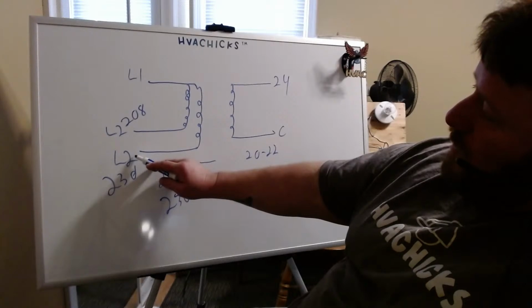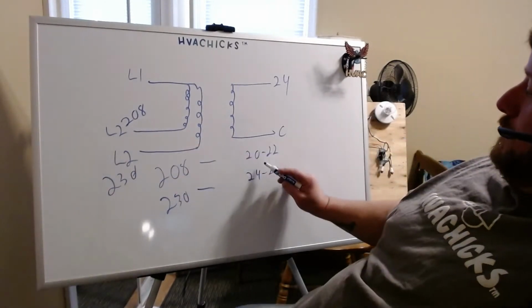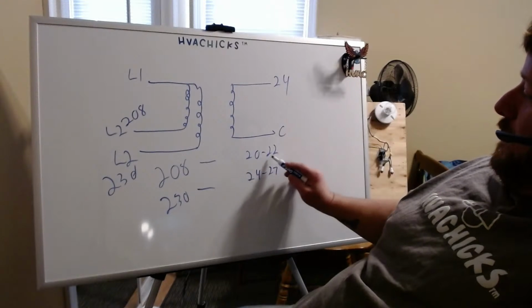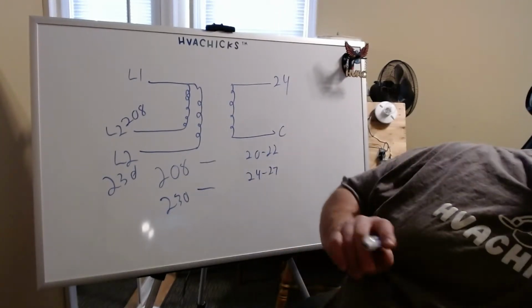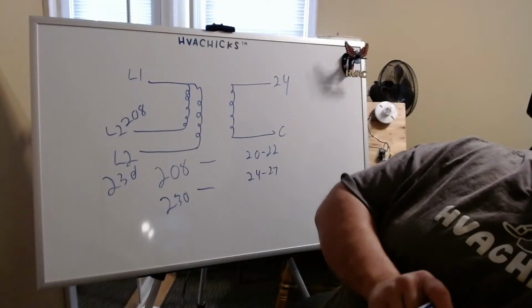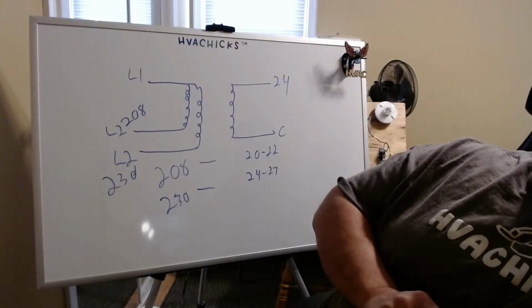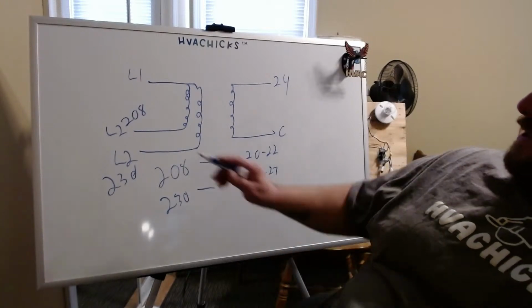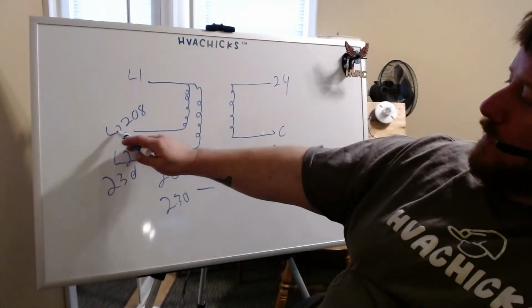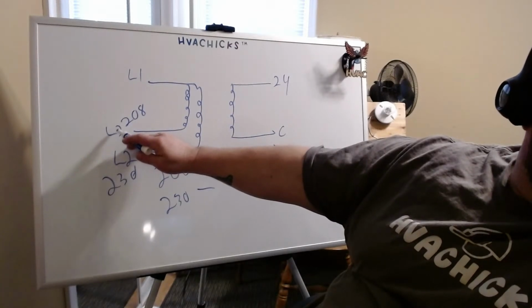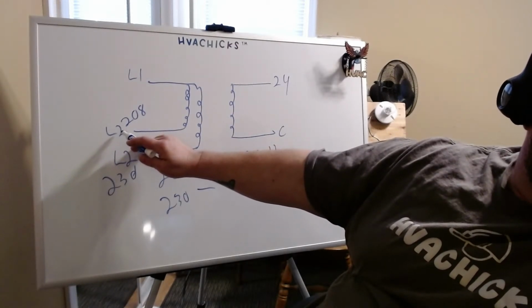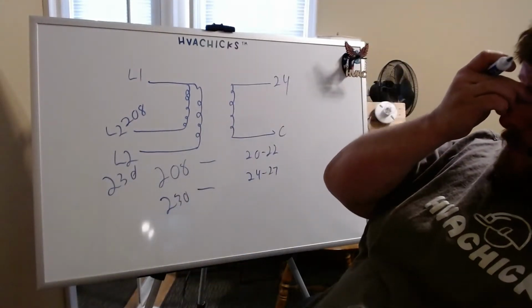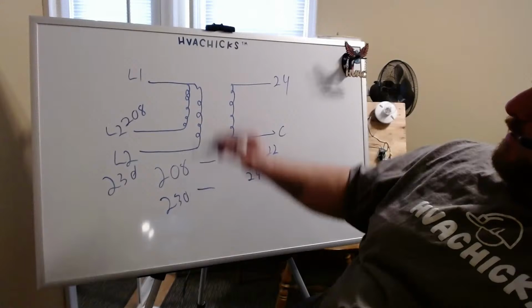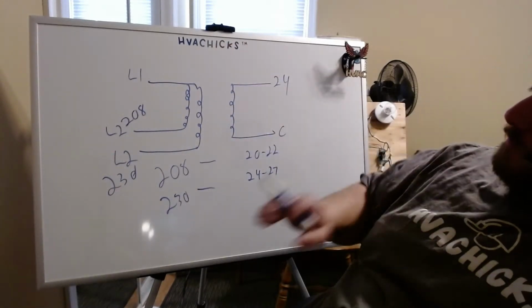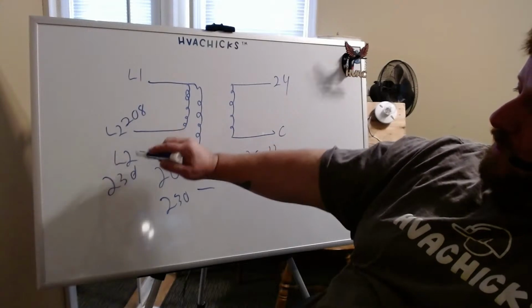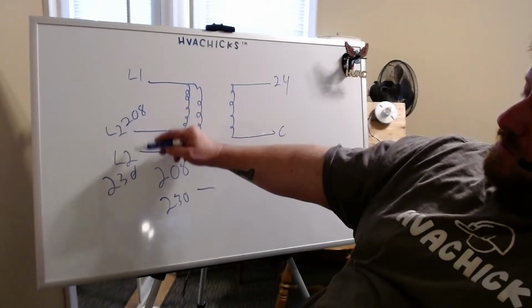If I don't move this 208 wire over to the 208 tap, I'm going to be getting this voltage right here. It can cause contactors and relays to overexert themselves to try to get the 24 volts to close those coils and make them work properly. So you really need to make sure you're wiring your high voltage on those commercial package units to the 208 circuit if it's 208. Okay. Now, sometimes with three phase, you'll have different circuits coming into it, different voltages. But for the main thing, you want to make sure that this is correct.